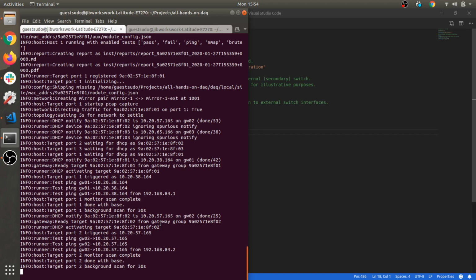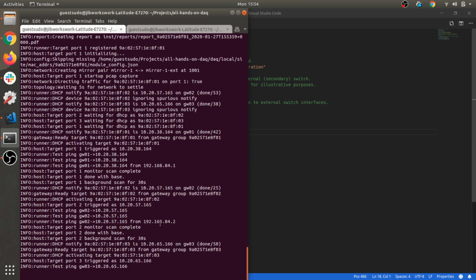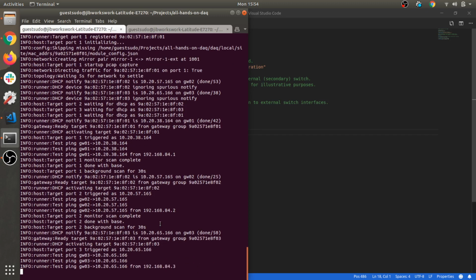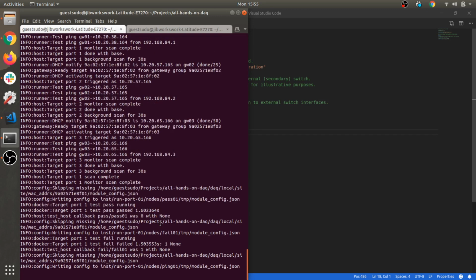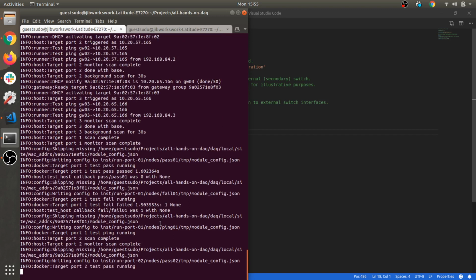This is in stark contrast to how a lot of current building devices and older IP connected devices work, in that they don't have DHCP turned on or even implemented. So you must define a static IP on the device before you even plug it in, which is not very useful on a highly dynamic network.